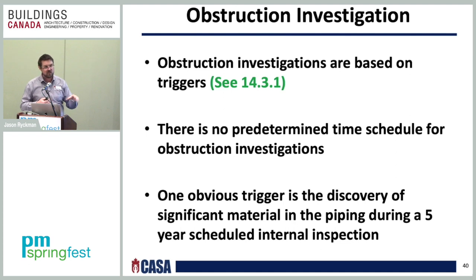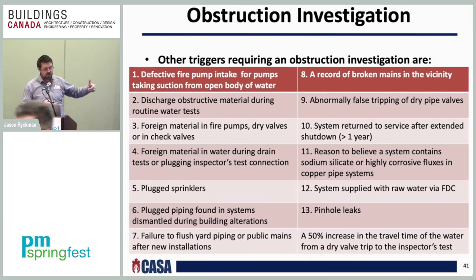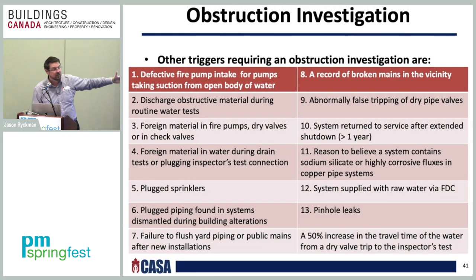While internal inspections are on a timely basis, as we mentioned, every 5 years, there is no time requirement for an obstruction investigation. They are solely based on what we call triggers. And this was very confusing in the editions prior to the 2011 edition of NFPA 25. So some of those triggers include the following. There's a total of 14 different triggers, okay?